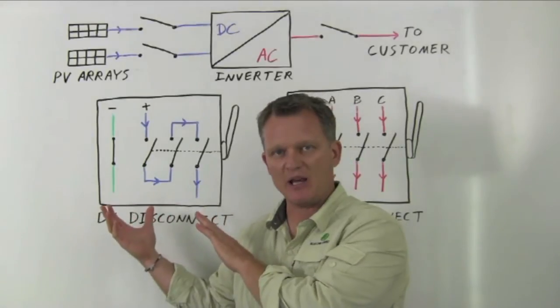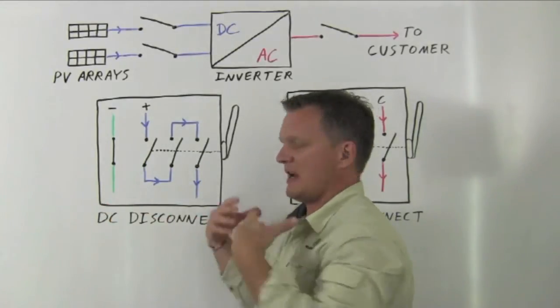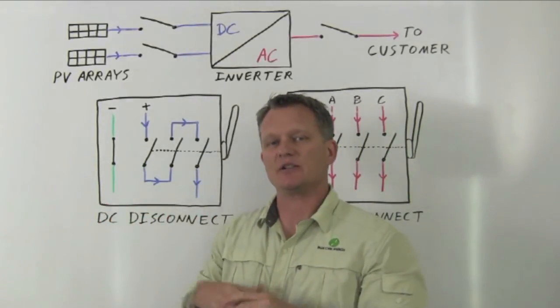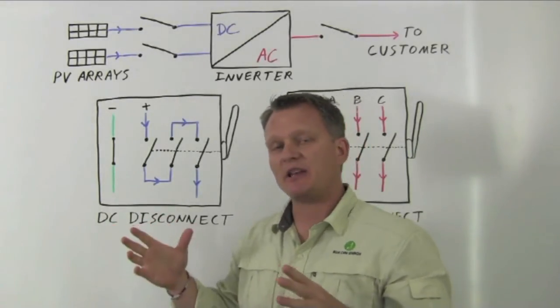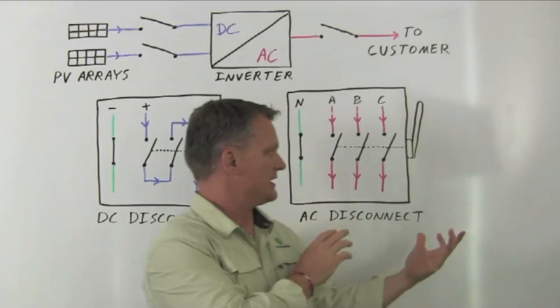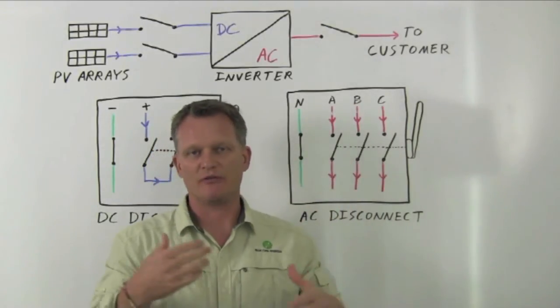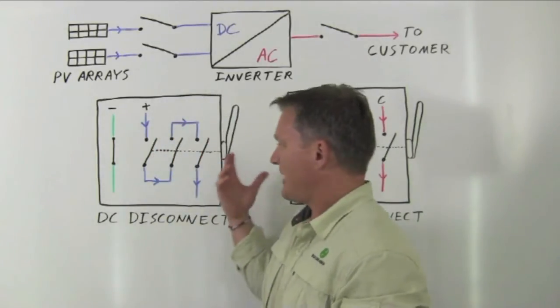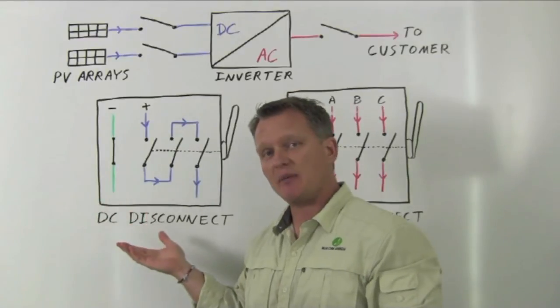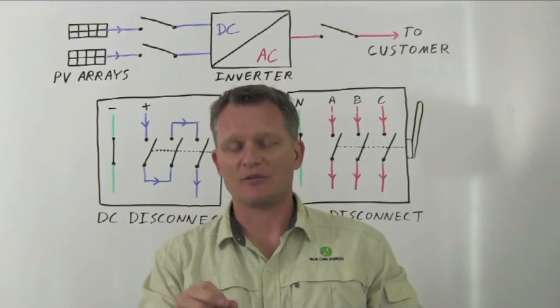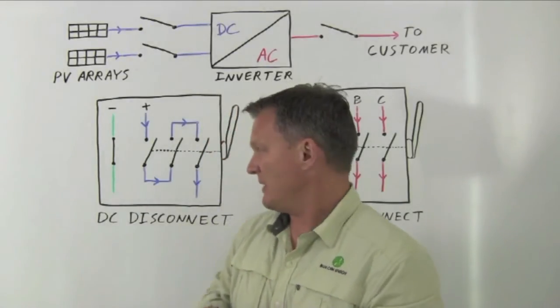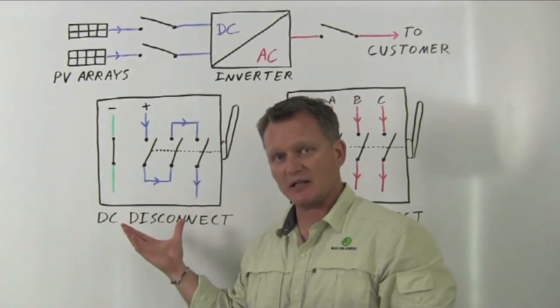So the key here, though: every manufacturer makes a version of an AC disconnect that comes in multiple poles of different numbers, and some of them can be used in DC applications. The lesson to take away from this is that you need to read the manufacturer's installation instructions. Make sure if you want to use their disconnect in a DC application.